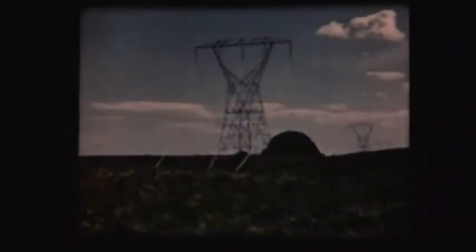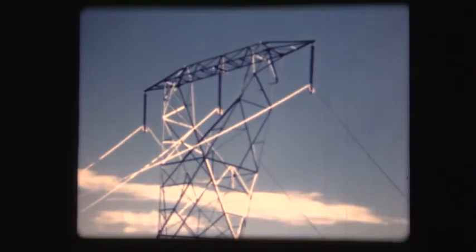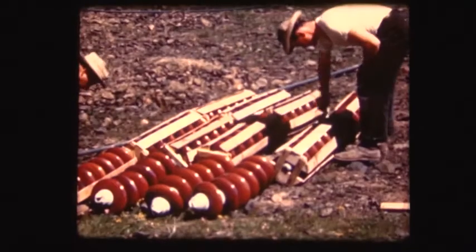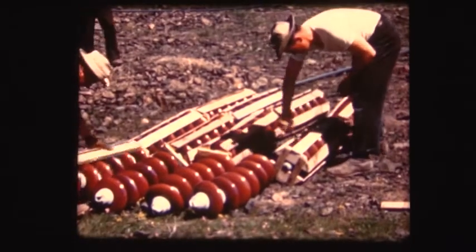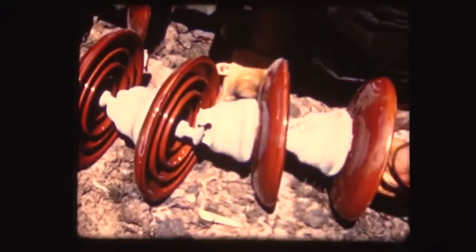When the stringing operation has been completed, we have a section of line with the conductor hanging loosely in the shivs. The next operation is sagging. That is, pulling the conductor up to the sag specified in the stringing manual. Before the line is sagged, it must be made fast at one end. In most situations, this can be done by securing it permanently to a dead-end tower.